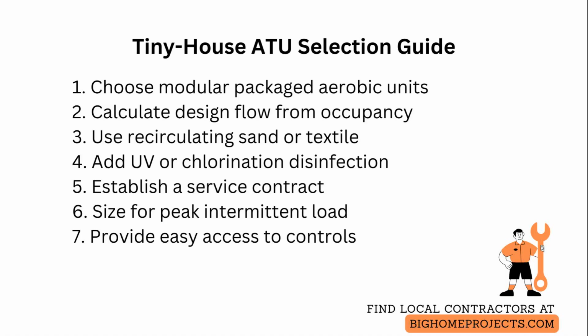Use a recirculating sand filter or a textile filter after the aerobic unit when site soil or setback limits do not permit a conventional drain field, because these filters provide additional solids and biological polishing in a compact footprint.